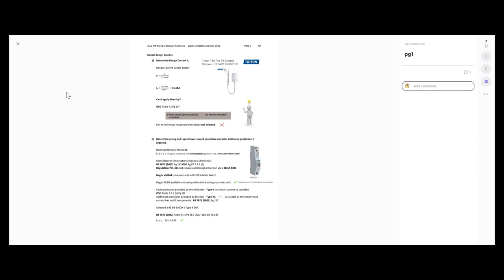I know I need a 30 milliamp device for additional protection, so the RCD part of this RCBO — I've got to consider what type I need. Does it need to be Type A, B, F, or can it be Type AC? When we look in the regs, it talks about whether the equipment can introduce DC. Because it's a purely resistive load, it doesn't have any DC components — therefore we can use a Type AC, the symbol being your sinusoidal waveform. This shower has no electronics in it, so it can be on a Type AC.